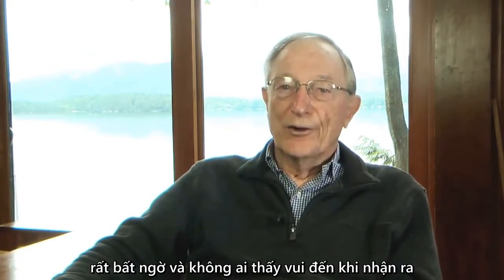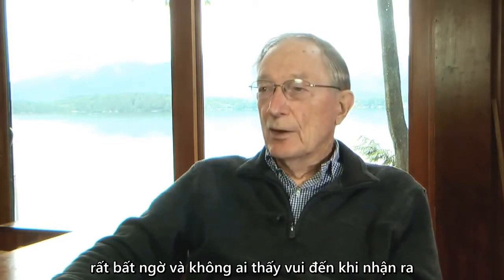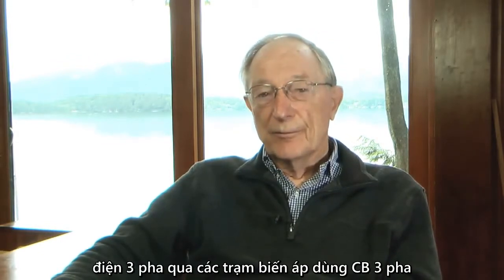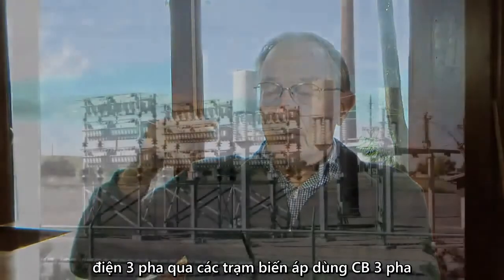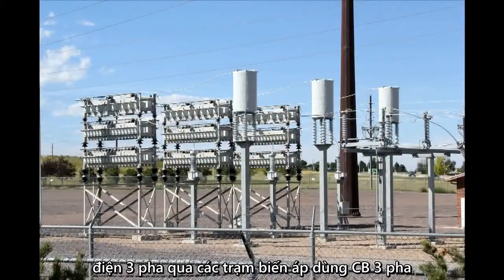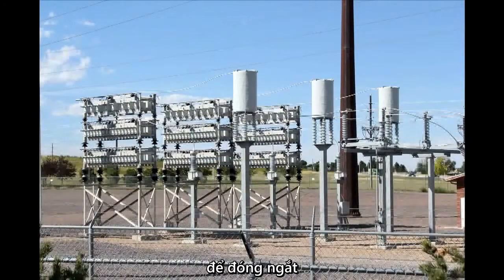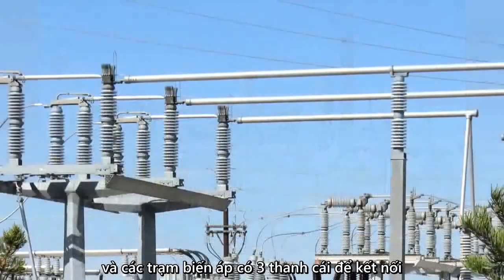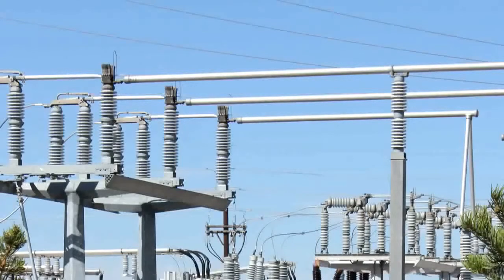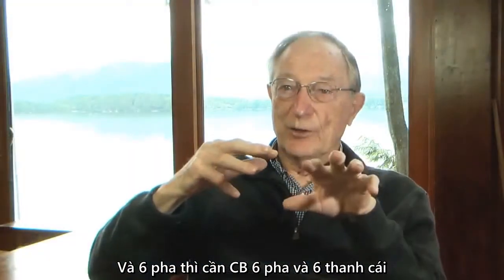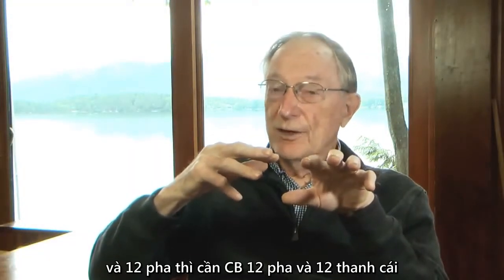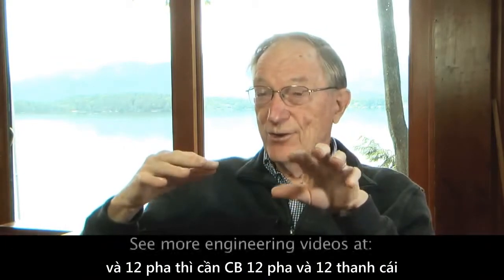And one got a little excited about it until you realize that a 3-phase line, when it goes into the substation, has 3 circuit breakers to open it, close it. And throughout that substation, there are 3 bus bars that these connect to. With a 6-phase line, there would be 6 circuit breakers and 6 bus bars. 12 phases, there would be 12 circuit breakers and 12 bus bars.